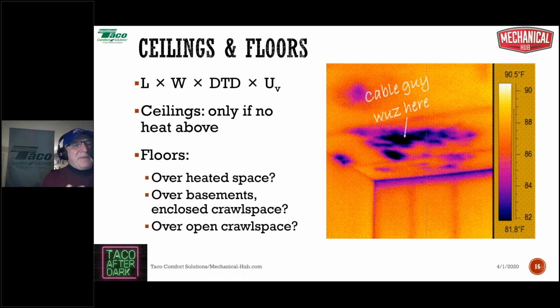Think about it - in a basement, it's not 0 degrees, it's more like a constant 55 or thereabouts. If you did a heat load through the floor with 70 here and 55 there, that's a design temperature difference of only 15 degrees. That number would come out so low it'd be more than offset by a person walking into the room - remember, your body with clothes on loses about 400 BTUs per hour at rest or light activity. So in those two instances, you don't need to do a floor loss, simply because it's not 0 degrees down there.